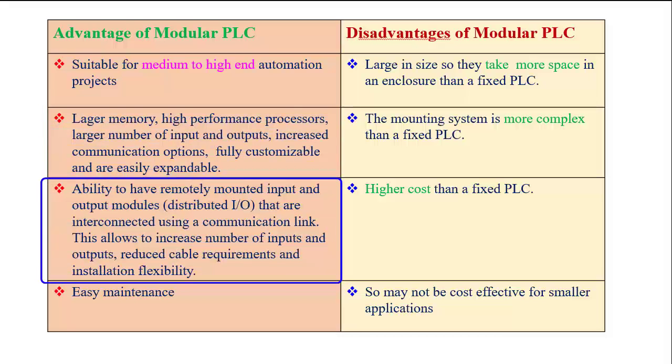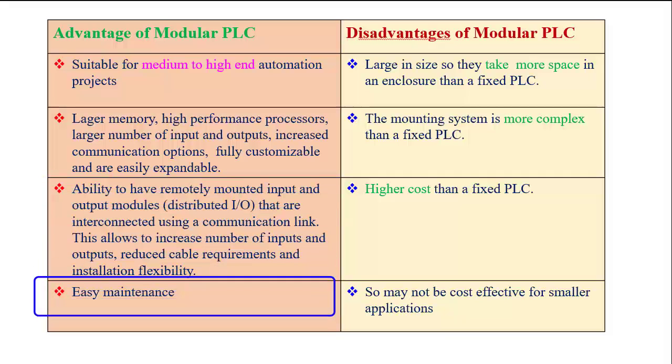It has the ability to have remote mounted input and output modules, which may be defined as distributed I/O that are interconnected using a communication link. This allows an increase in the number of inputs and outputs, reduces cable requirements and gives installation flexibility. And maintenance in this case is very easy. We just need to replace or change the hardware modules and make a little bit of programming modification.